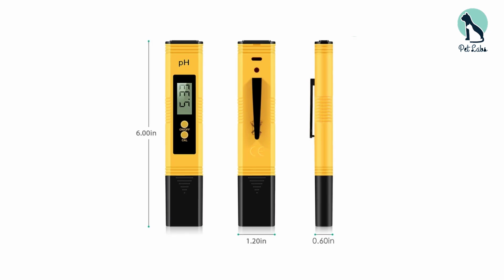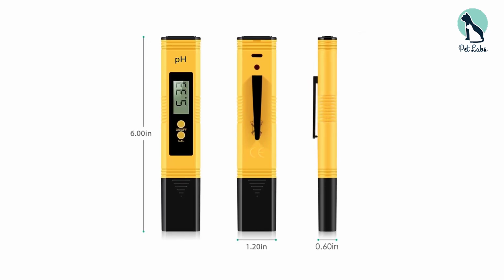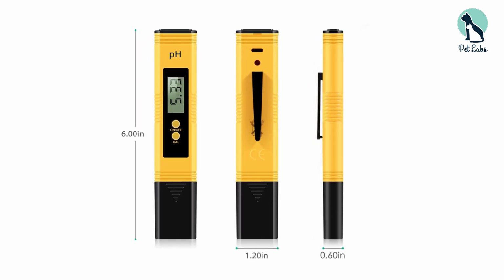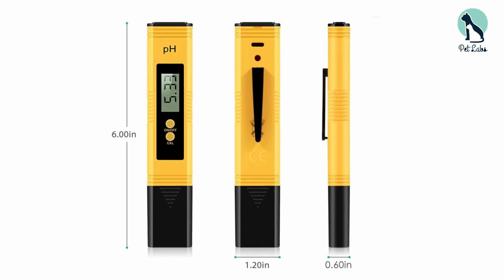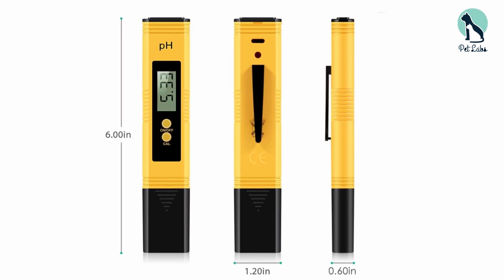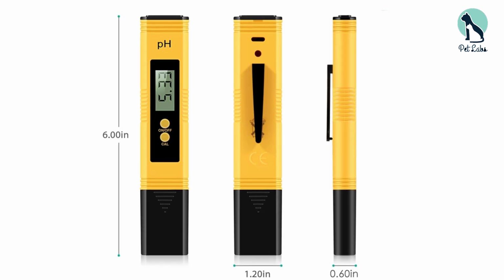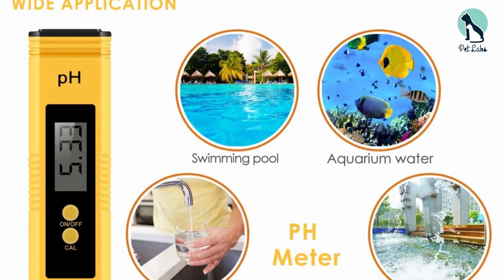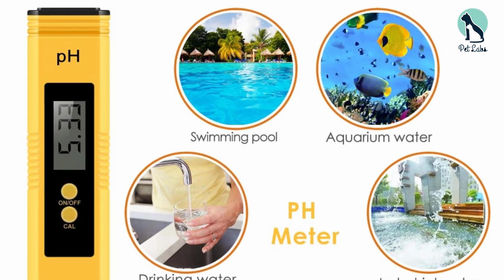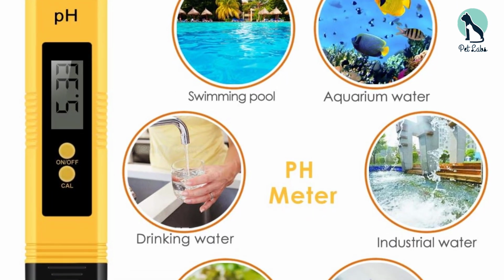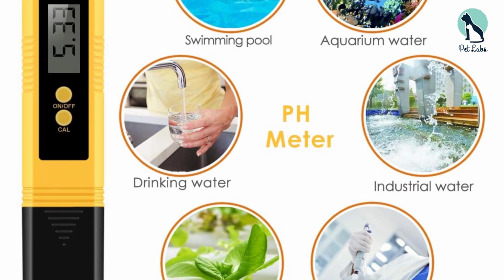The meter also comes pre-calibrated, so you can use it as soon as you receive it, though you'll want to recalibrate it weekly. A carrying case is also included for safe storage of the pH meter. However, while the store page says that it has an accuracy of plus or minus 0.01, this can vary after extended use, growing more inaccurate over time.